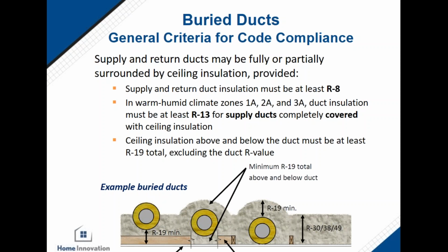So potentially, let's say there was a rip in the outer jacket of the outer duct. In the case of the concentric ducts, could moist air get in there and condense on the next surface? Yeah, possibly. On the other hand, I think it's unlikely, because the duct on the inside should be your R8 duct anyway. So you're still protected with a sealed vapor barrier, and you have R8 insulation between that point and the inner liner of that main duct.